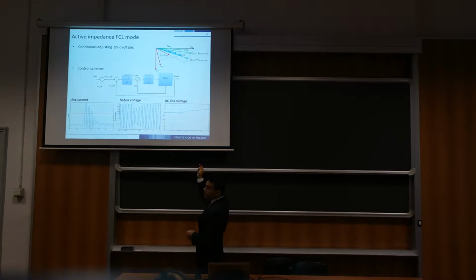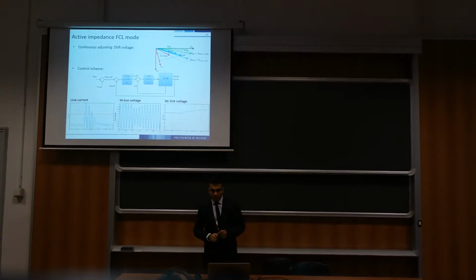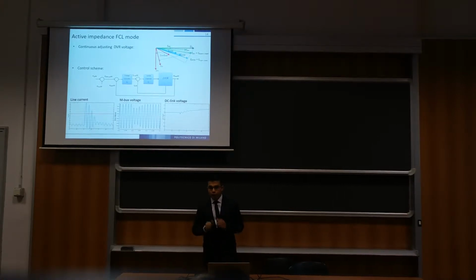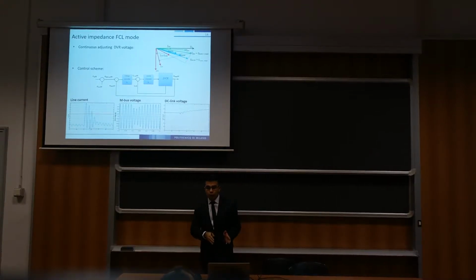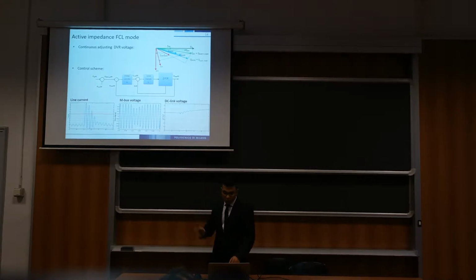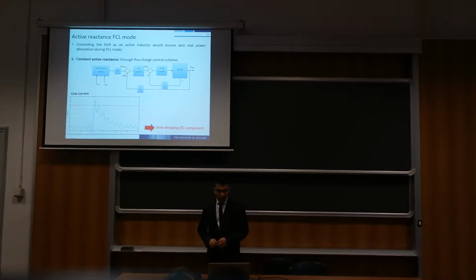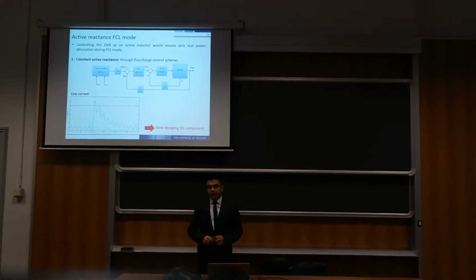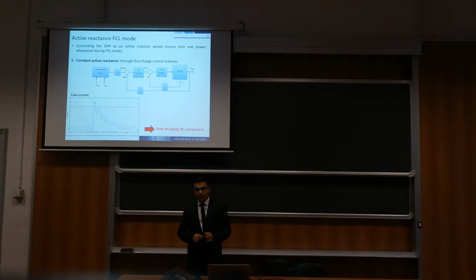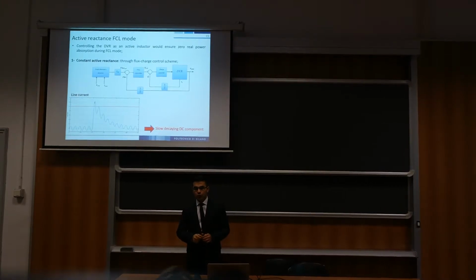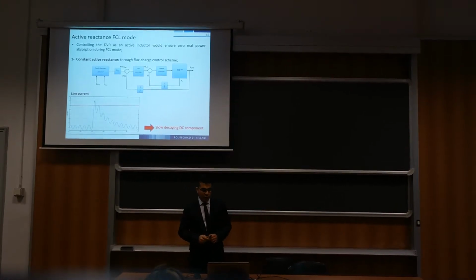But regarding the DC link voltage, because the DVR is controlled as an impedance, it absorbs power during short circuit fault current limiting function, so the DC link voltage increases, which could be a matter of concern. A solution could be a dissipative strategy in order to limit this voltage increment. Controlling the DVR as an active inductance would ensure zero real power absorption during fault current limiting function.